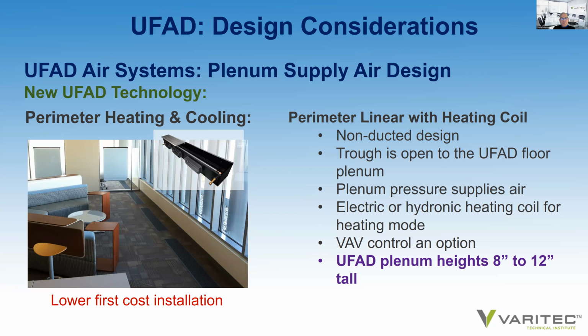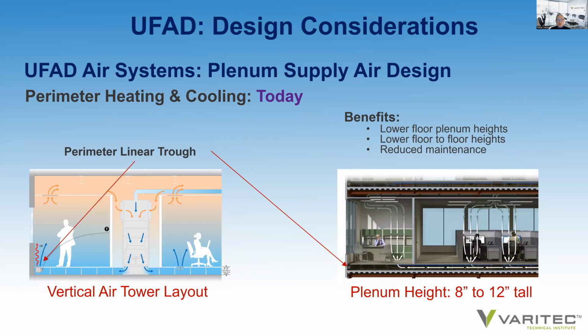And it certainly reduces the mechanical maintenance of systems underneath the floor. No more fan motors that need to be looked at. No longer would tiles have to be raised to evaluate and service fan-powered terminal units. Everything is serviced through the face of the linear trough register.